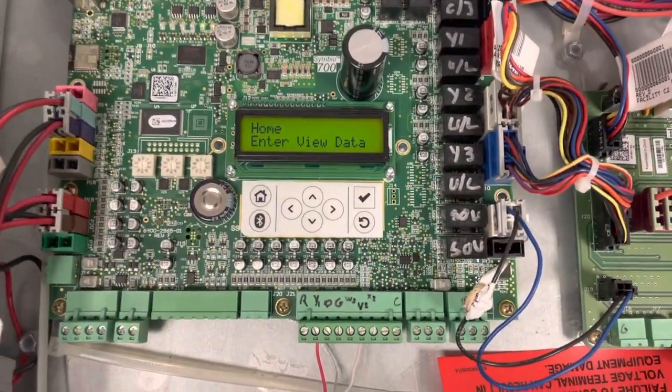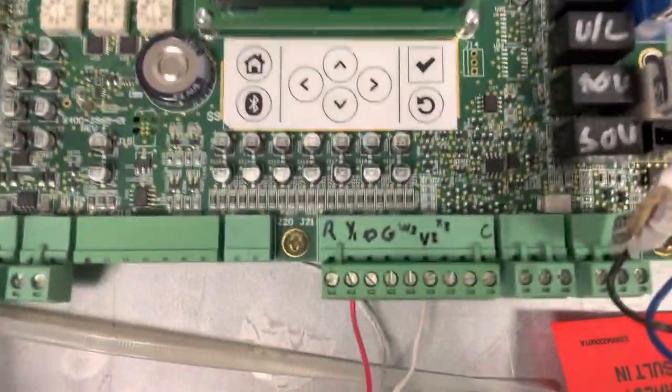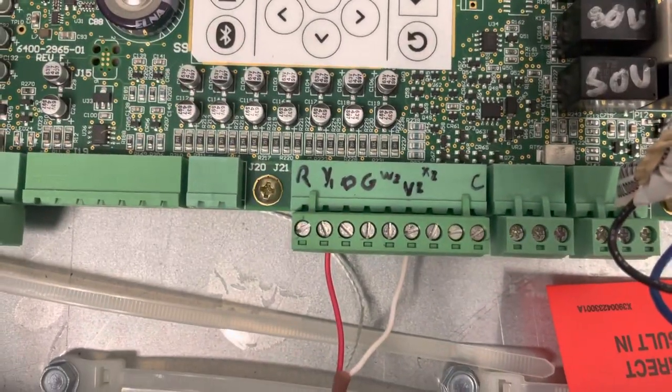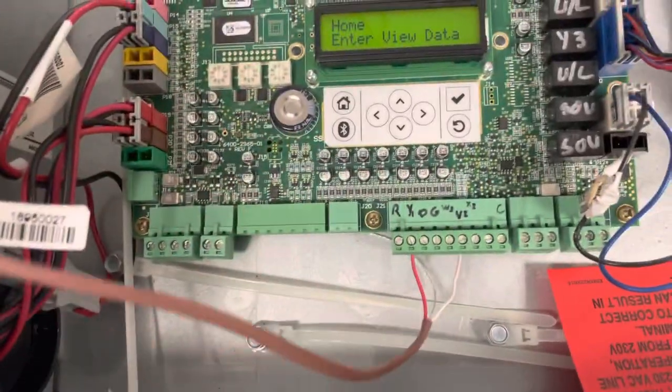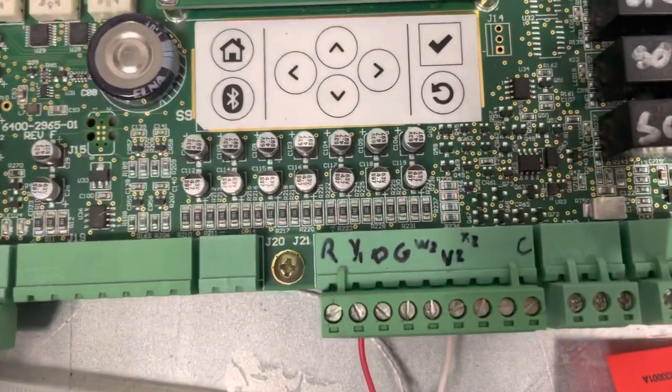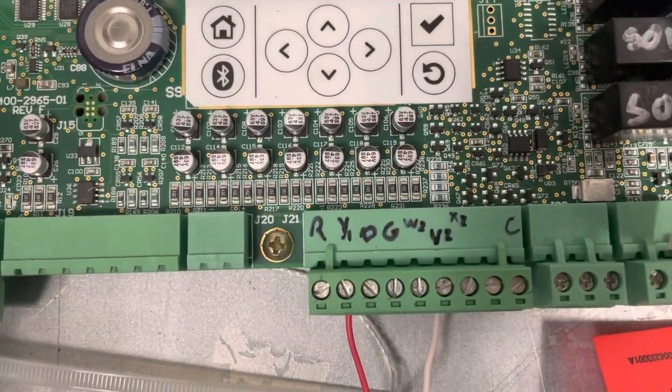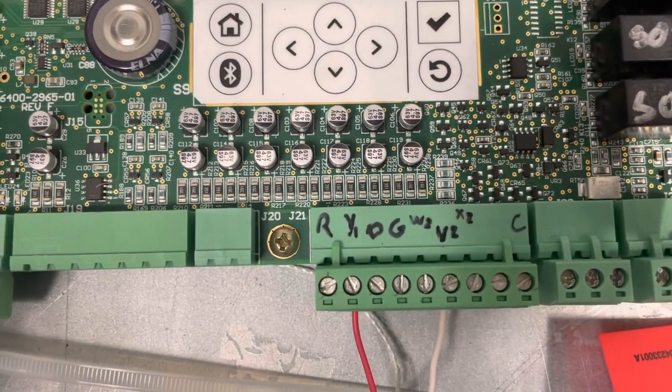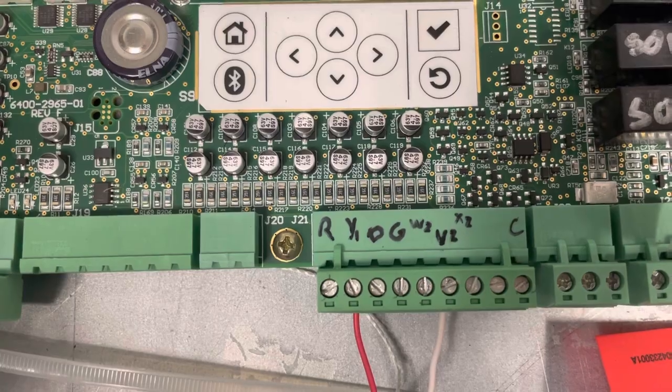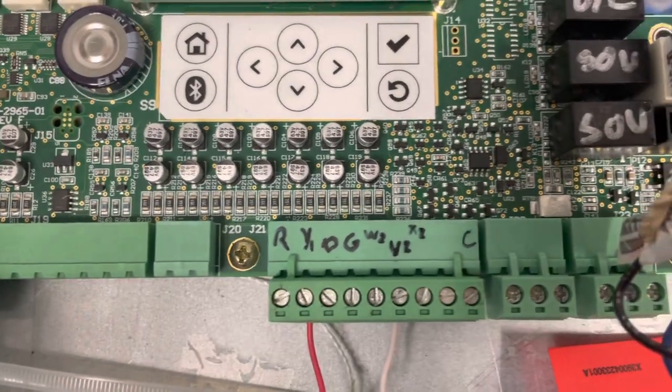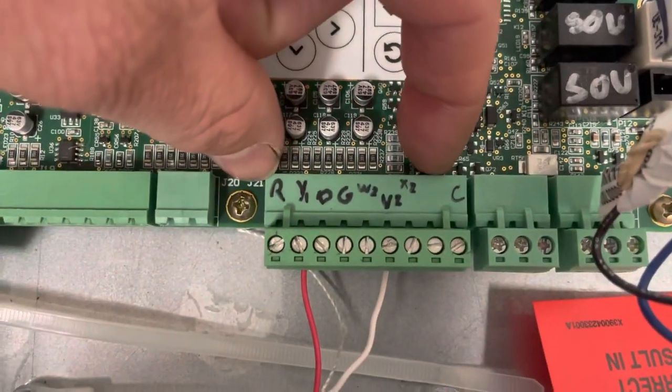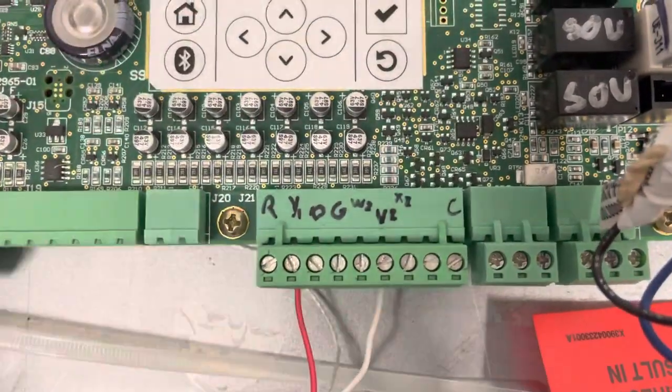If you can see, I've got my two wires, so this would be the two wire strand coming from the indoor unit to the outdoor unit. In this case, I hooked it up to Y1 and Y2. So if you have a two-stage condenser, you can configure it this way, nothing coming off any of the other terminals that would connect to the thermostat.